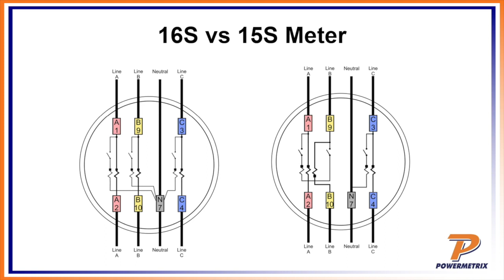With this old 15S mechanical meter, what they did is support a delta service. You can still support this on a 4-wire delta, they still call it a 15S, but I'm not sure why, I think that's a misnomer. At that time it had two voltages, phase to phase: 240 volts VAB, and then your high leg, which is 208, or if you had 277 volt service coming in. So it's a very specialized service.